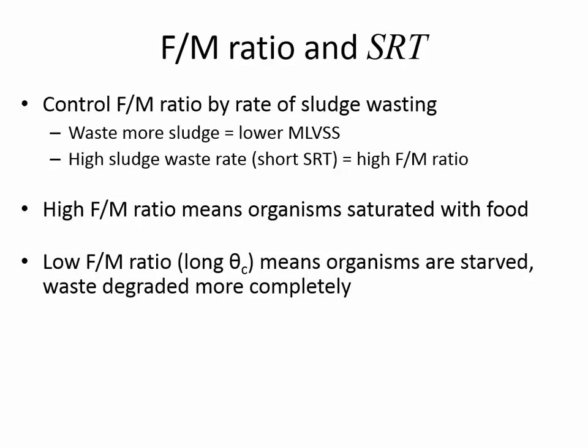Instead of only breaking down the substrate, instead of only breaking down the soluble BOD, the microorganisms are sort of cannibalizing one another. And so if you have a long solids retention time, you have a much more diverse population of microorganisms, and that degrades the waste more completely.